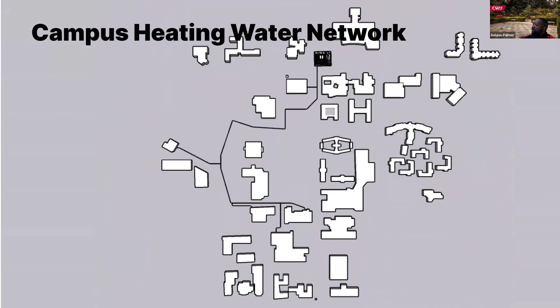Our existing central energy plant is the small box all the way to the left of your screen. The cooling water network is the chilled water system that serves the majority of campus. We'll be taking advantage of this to push new chilled water from both the GEP and our central plant across campus. We have four 1,200-ton chillers in our central energy plant, so cooling capacity is not really an issue for our university. This shows a combination of what the campus heating and cooling water network looks like together.